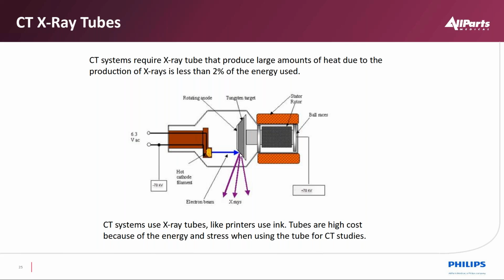Most X-ray tubes used in CT have a 7-degree target angle. When we get into the scanners that are 128 and higher, especially the 256 ones, that will change to 11-degree target angle because of the spread getting to all the rows of detector elements. So we have a rotating target, tungsten target. This shows 1 filament. Most X-ray tubes have 2 filaments.